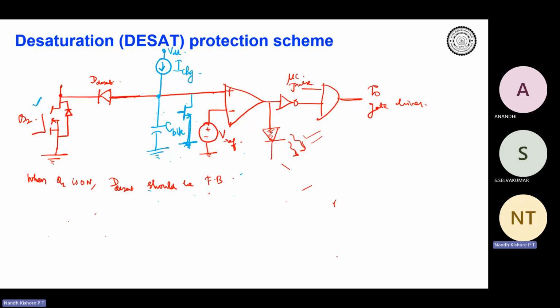And we have even seen that DSAT has probably false triggered, just like that the LED turned on. Let's run the circuit again. Again, the DSAT LED will glow. That time we know that definitely some device has gone bad, which is why DSAT is triggering again and again. Do you understand? That's how you come to know that the device has failed. So this is one of the ways.